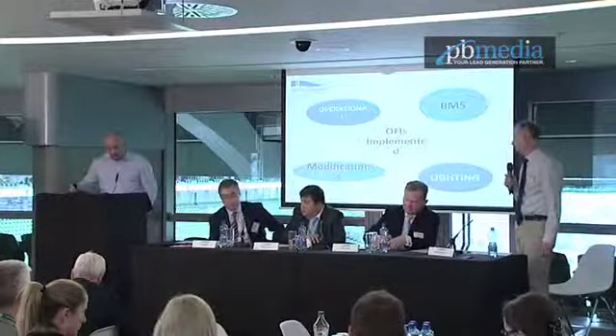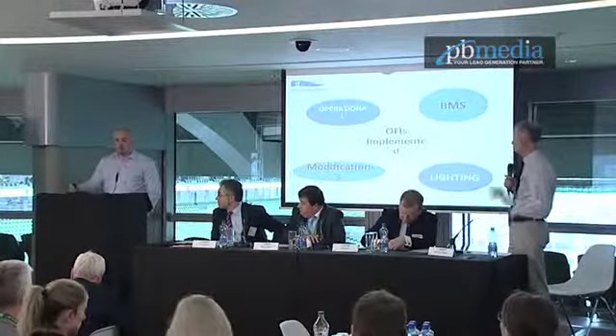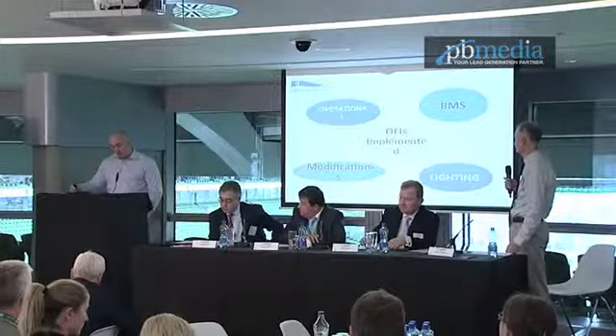So one of the main OFIs that I believe had probably the most impact on our energy reduction had to do with how the BMS controlled all the plant and equipment, specifically for HVAC in the stadium. Originally, the designers had it such that it was targeted more for match day. So when you had 50,000 people in the stadium, it ran enough plant to achieve the temperatures that you needed. But we had a look at it after it was handed over to us, and we found that if you wanted to run a conference, much like the conference we're doing today, too much plant ran. A lot of waste, so air handling units, fans.